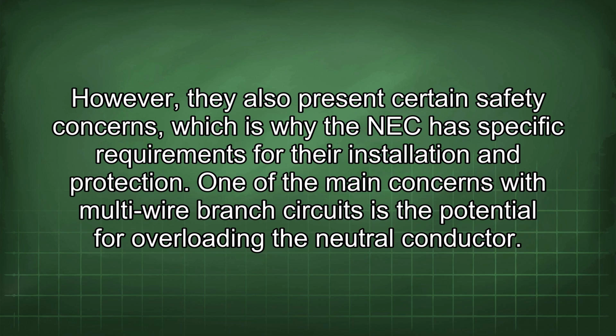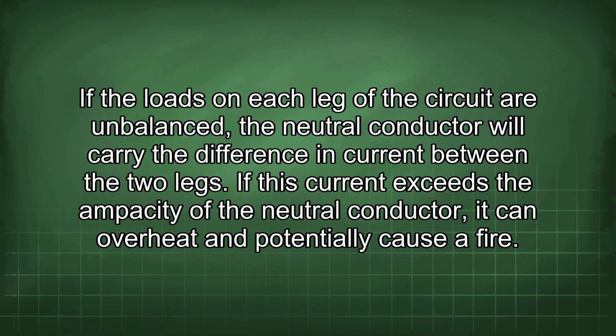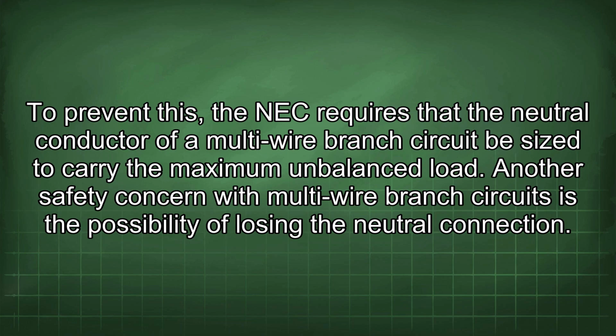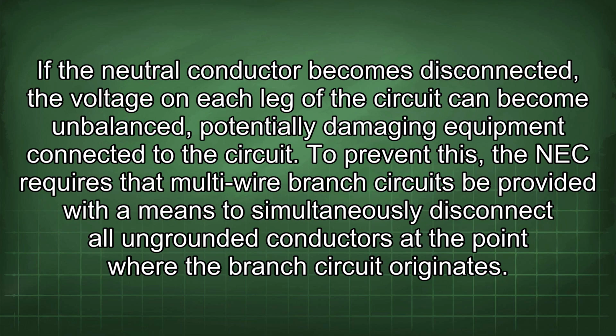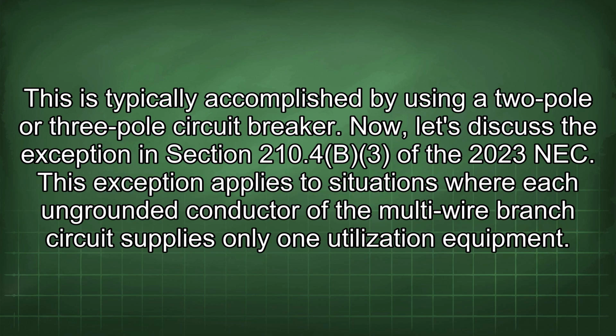One of the main concerns with multi-wire branch circuits is the potential for overloading the neutral conductor. If the loads on each leg of the circuit are unbalanced, the neutral conductor will carry the difference in current between the two legs. If this current exceeds the ampacity of the neutral conductor, it can overheat and potentially cause a fire. To prevent this, the NEC requires that the neutral conductor of a multi-wire branch circuit be sized to carry the maximum unbalanced load. Another safety concern with multi-wire branch circuits is the possibility of losing the neutral connection. If the neutral conductor becomes disconnected, the voltage on each leg of the circuit can become unbalanced, potentially damaging equipment connected to the circuit. To prevent this, the NEC requires that multi-wire branch circuits be provided with a means to simultaneously disconnect all ungrounded conductors at the point where the branch circuit originates. This is typically accomplished by using a 2-pole or 3-pole circuit breaker.